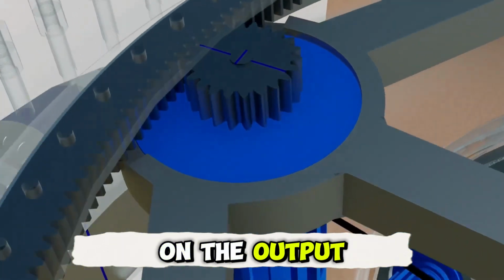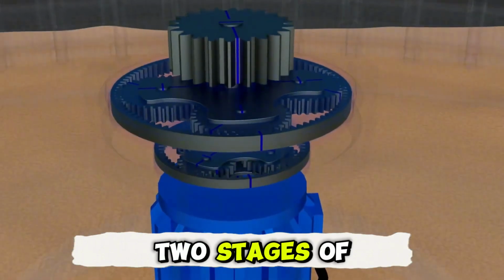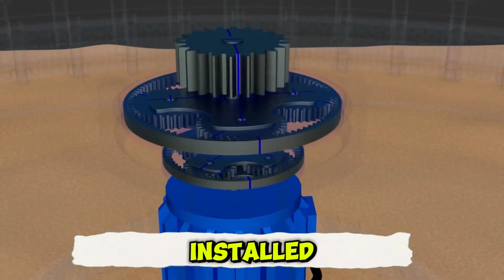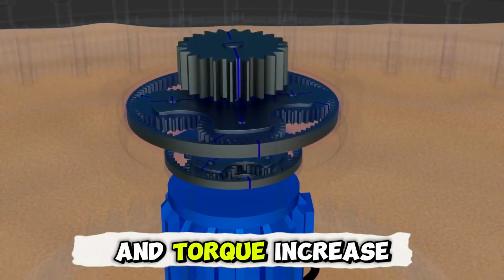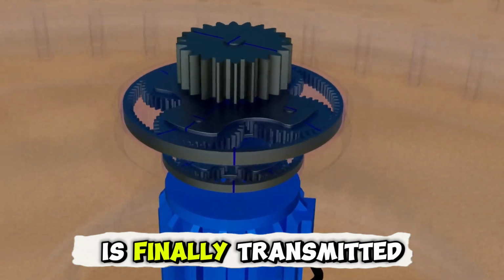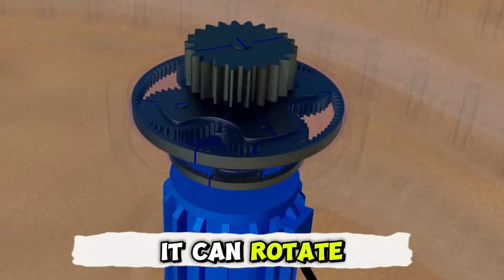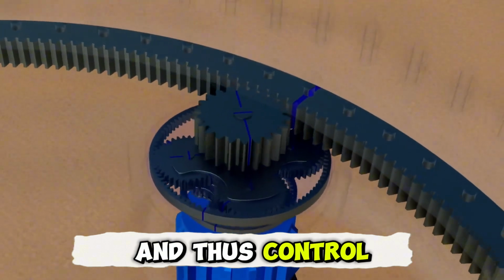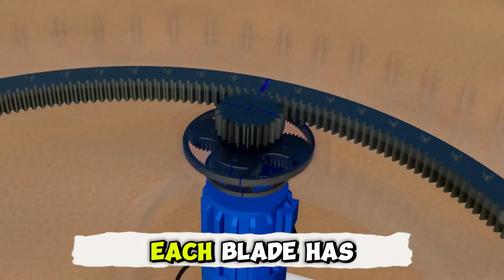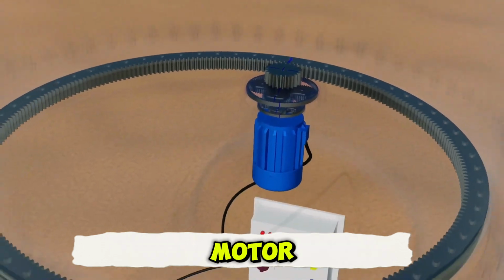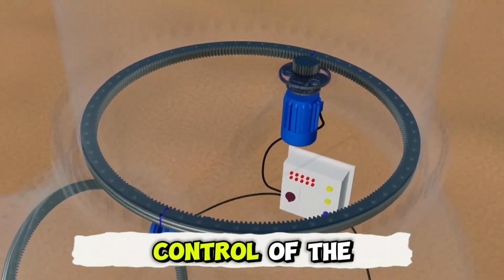Therefore, on the output shaft of the motor, 2 stages of planetary gears are installed to achieve deceleration and torque increase. When the power is finally transmitted to the bearing, it can rotate the blade angle and thus control the rotation speed of the blade. Each blade has such an independent motor to achieve independent control of the blades.